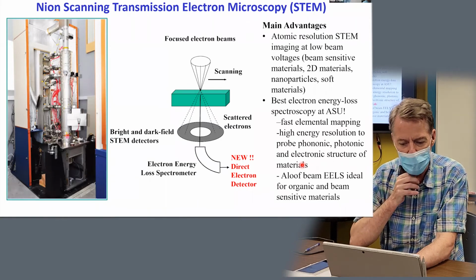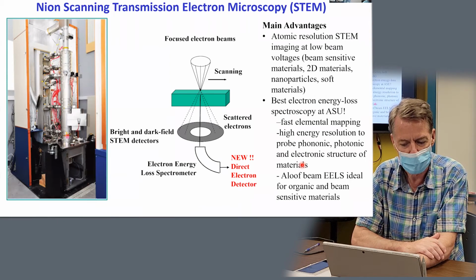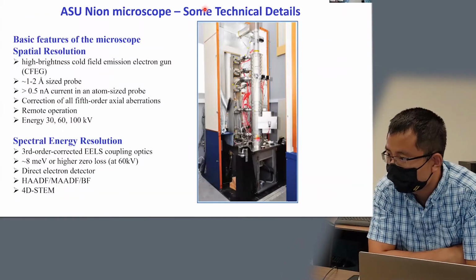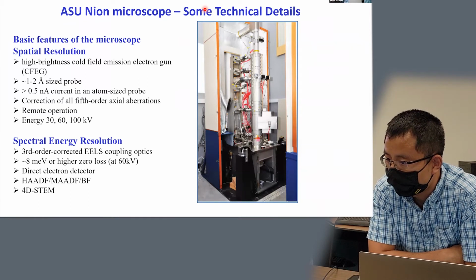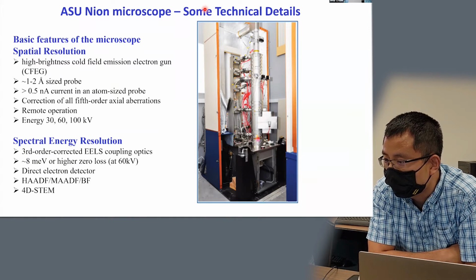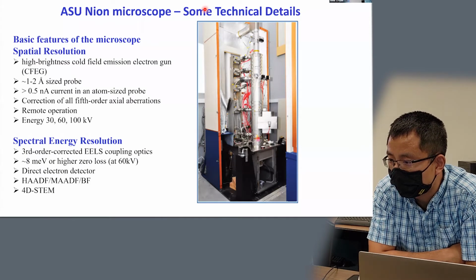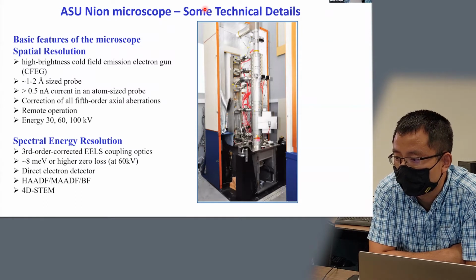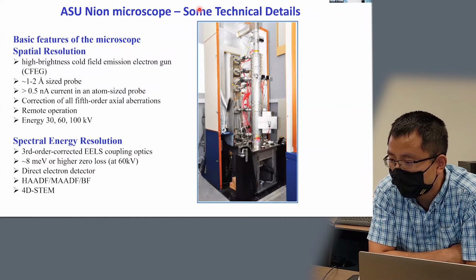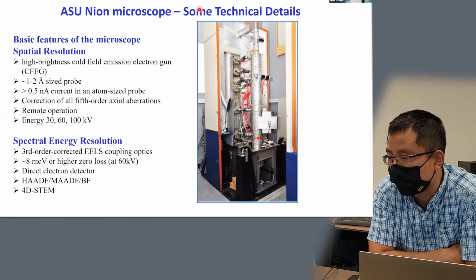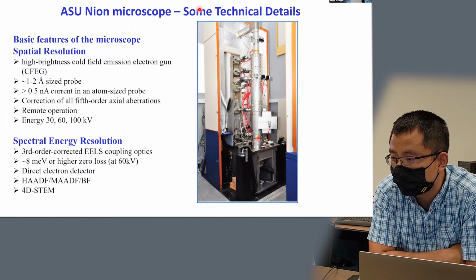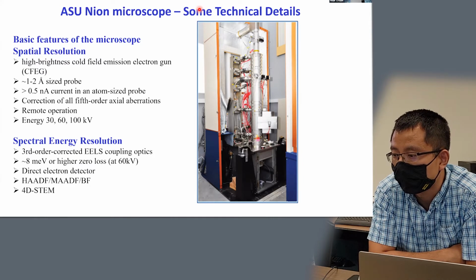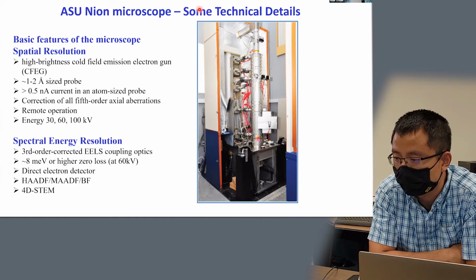To tell you a little bit more about this, I'm going to hand the floor over to Shize. So I'll introduce some technical details of the microscope. The ASU Nion Microscope is equipped with a high brightness cold field emission gun, which offers a very decent atomic size probe, about 1 to 2 angstrom, at a high current larger than 0.5 nanoampere. The aberrations can be corrected up to the 5th order, and it operates at 3 different voltages of 30, 60, and 100 kV, which is good for beam-sensitive materials.